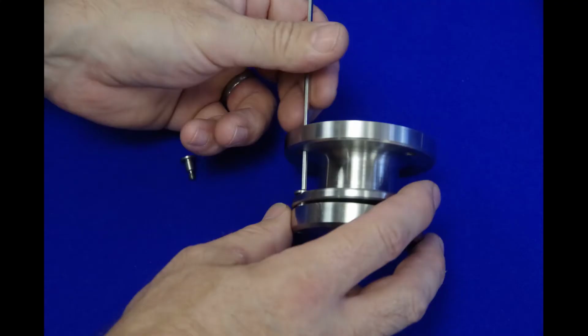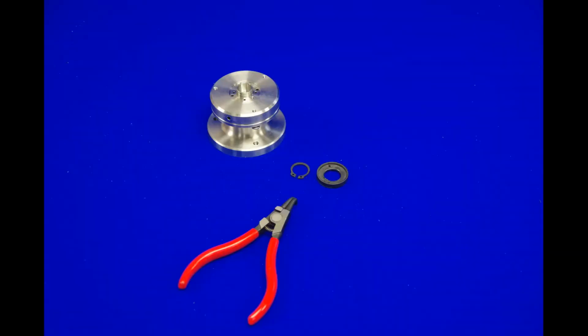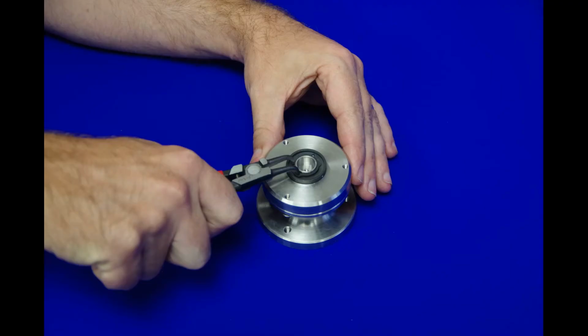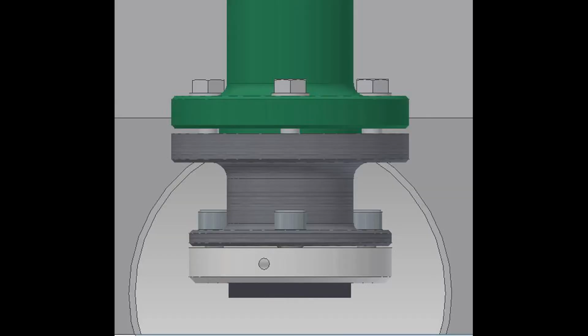The upper specimen assembly is in two parts: a hub adapter that connects to the spindle flange and a specimen carrier disc. The hub and the disc are loosely connected by 3 shoulder screws, which allow the specimen disc to self-align with the lower specimen. Fit a thrust washer specimen to the upper specimen holder using an external circlip. Next, attach the assembly to the spindle flange with the 3 bolts.